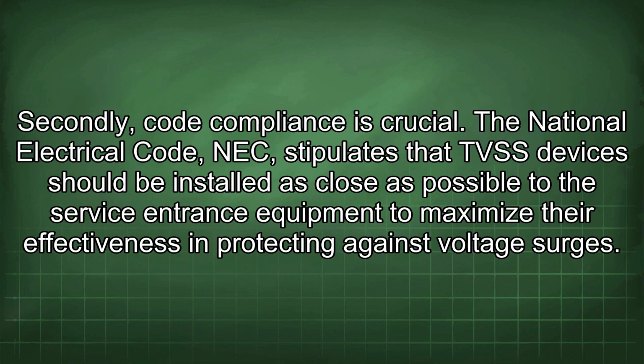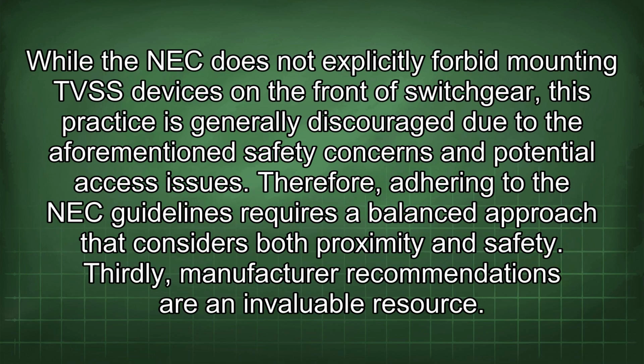Secondly, code compliance is crucial. The National Electrical Code (NEC) stipulates that TVSS devices should be installed as close as possible to the service entrance equipment to maximize their effectiveness in protecting against voltage surges. While the NEC does not explicitly forbid mounting TVSS devices on the front of switchgear, this practice is generally discouraged due to the aforementioned safety concerns and potential access issues. Therefore, adhering to the NEC guidelines requires a balanced approach that considers both proximity and safety.